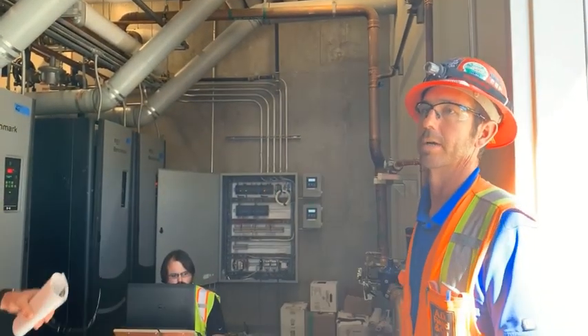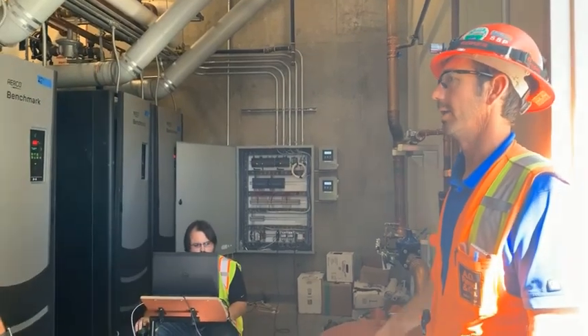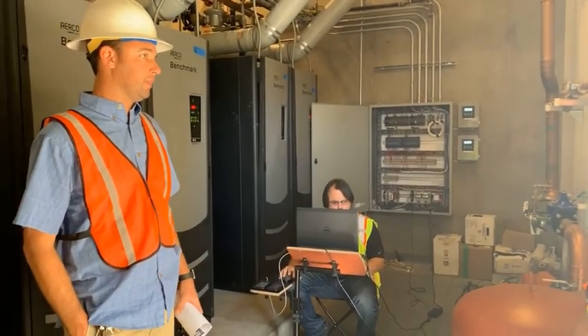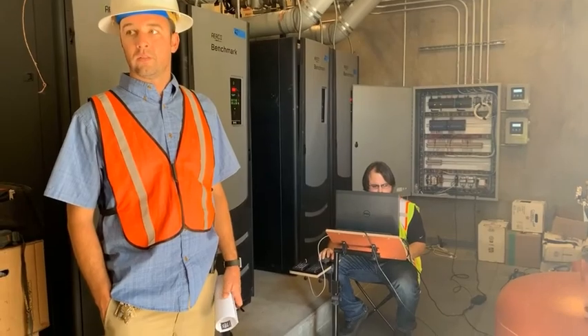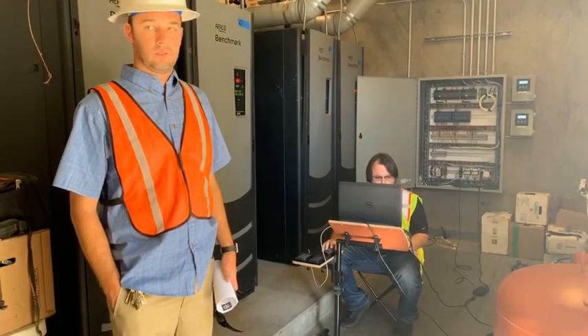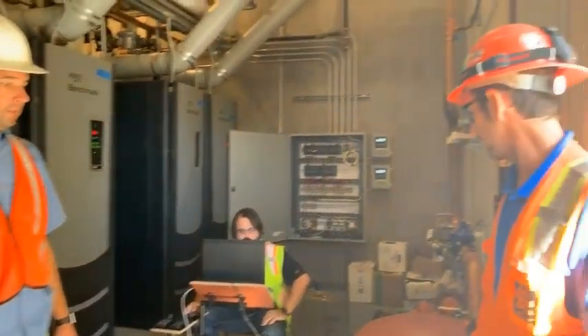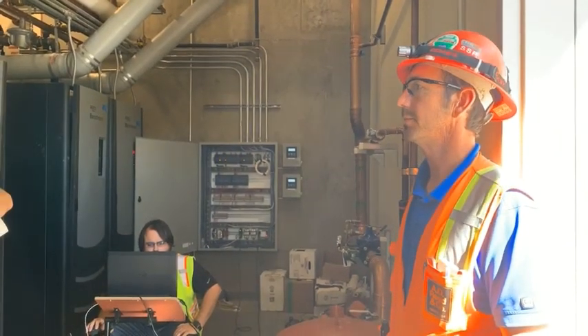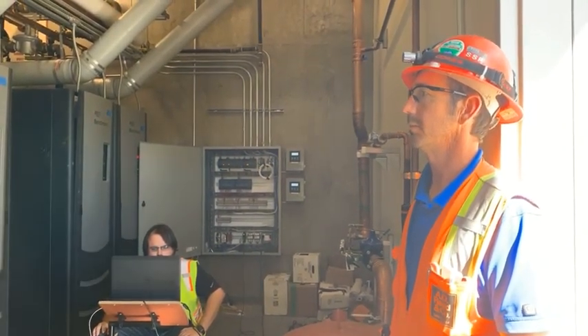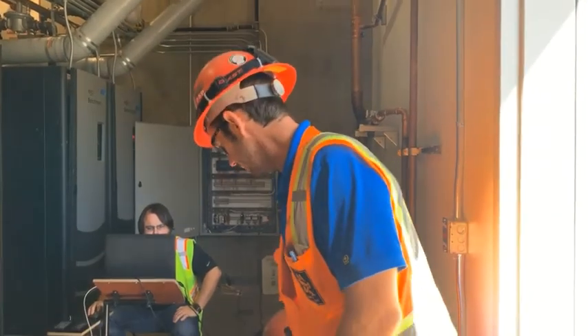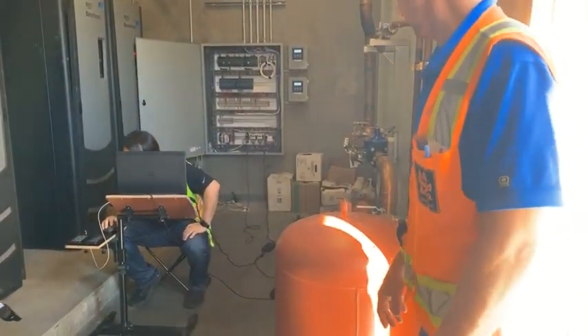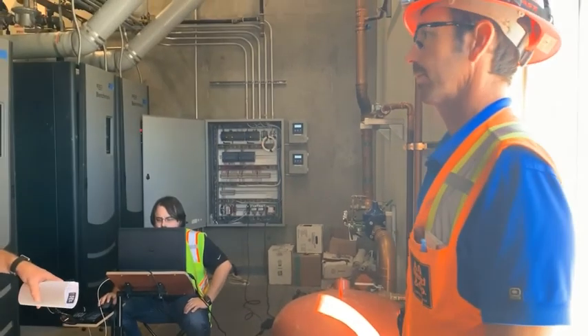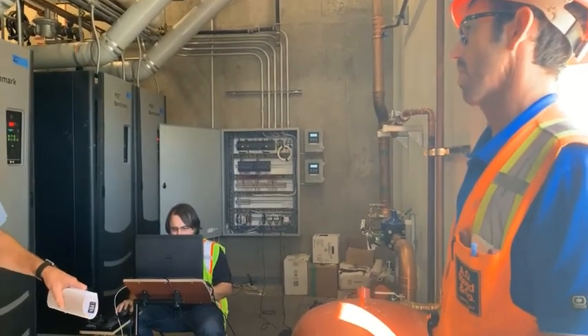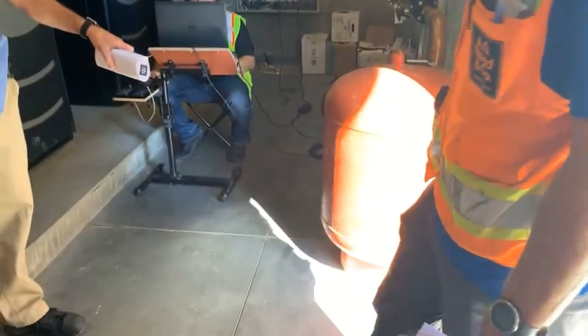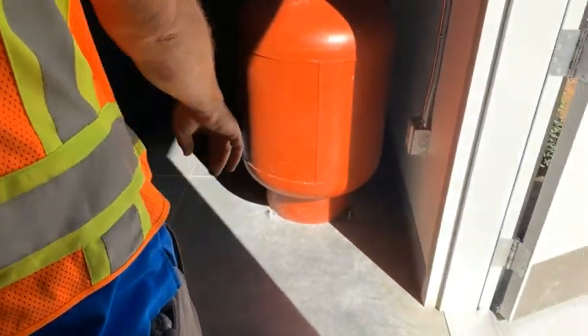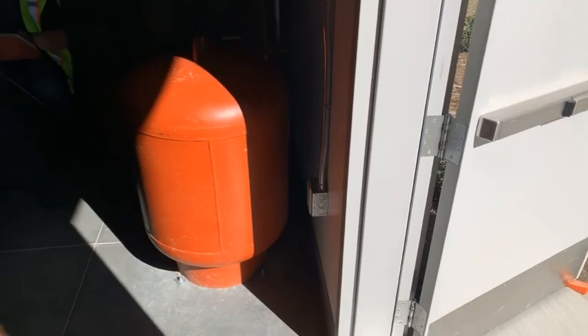So how do you change the bladder on this one? You have to replace it. It's easier just to replace it. We've replaced a bladder once before when Leonard was here up the hill. Sometimes you just unbolt it. This is a small unit. You replace the tank. I've replaced some that are bolted in, but this one, it looks like you can't even do anything, so you'll just undo it from the ground and grab a new tank. The tabs that are bolted to the ground like that, that's not factory on that tank though, is it? No, those tabs aren't. If we got a new tank, we'd have to re-weld the tabs on.